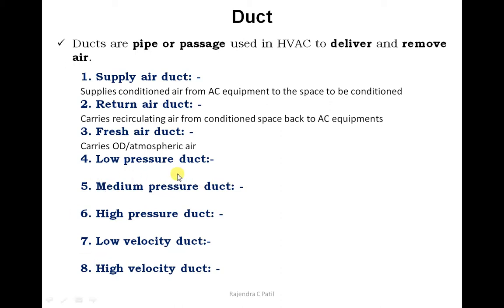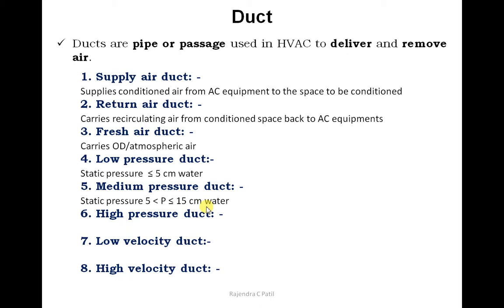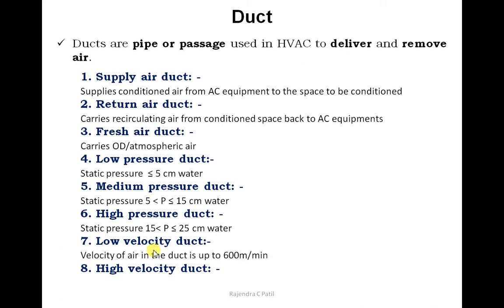Ducts are also classified on the basis of pressure. In ducts, pressure is always expressed in mm or cm of water column. When the static pressure of air flowing inside the duct is equal to or less than 5 cm of water, it is a low pressure duct. When it is more than 5 cm and less than 15 cm, it is a medium pressure duct. When static pressure is more than 15 cm, it is a high pressure duct. On the basis of velocity, if the velocity of air is up to or less than 600 m per minute, such ducts are called low velocity ducts.